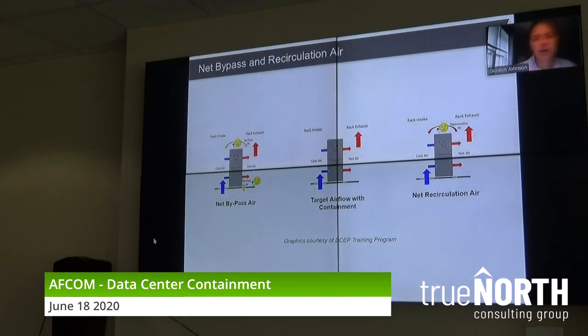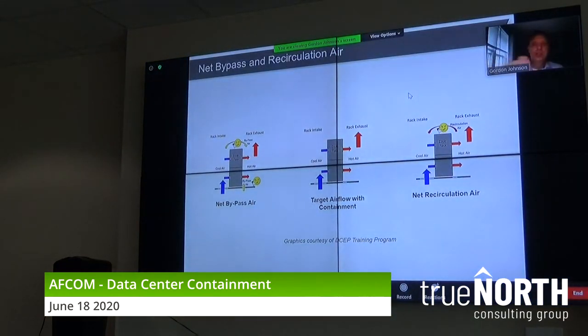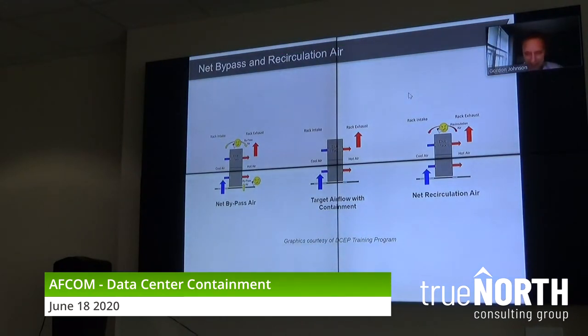Net recirculation air on the right is just as bad, because here's what gives you hot spots. Here's what causes server failures, IT alarms. We want that cold air to come to the IT intake. What we don't want is that hot exhaust air to deviate from going back to the CRACs. We don't want it to circulate above the top of the racks and back into the top equipment in the cold aisle. We don't want it to go around the end of the aisles and back into the first one or two racks at the edge of your cold aisles. That's net recirculation air.